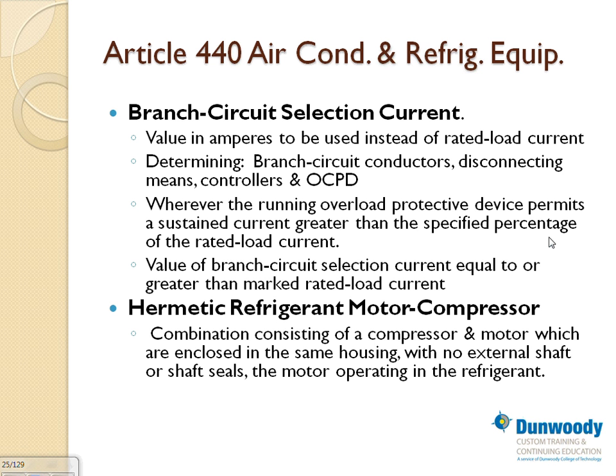We have branch circuit selection current. They use it instead of rated load amps. The way I understand it, I'm not an expert in HVAC, when you put a compressor pump with a blower, they can work harder than if you just have a blower by itself. Because of that, the current can be higher than the rated load amps for each one of them.